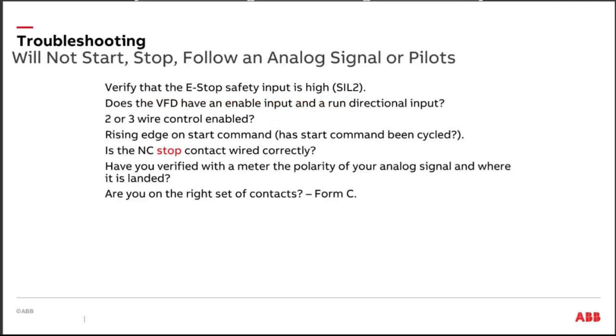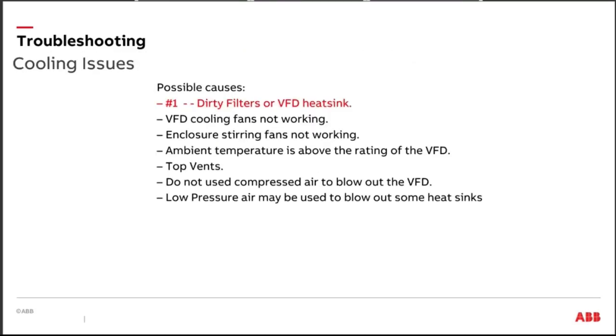And then the other thing to look at is, am I actually receiving my analog? Well, the drives that we have today, and I know ABB has it, and I suspect some of our competitors have it too, have a really cool I/O map, inputs and outputs map, built right into the keypad of the drive. You pull up your I/O map, and it's going to tell you what your inputs are programmed for, and whether that input is high or low. It'll give you a 1 or a 0. So when you start troubleshooting something like the drive is not starting, look at your I/O map and see if the drive thinks it's being told to run, or if it knows that we've got an analog coming into it. That's one of the neatest things in the world for troubleshooting a drive. Really cool feature that shouldn't be overlooked.